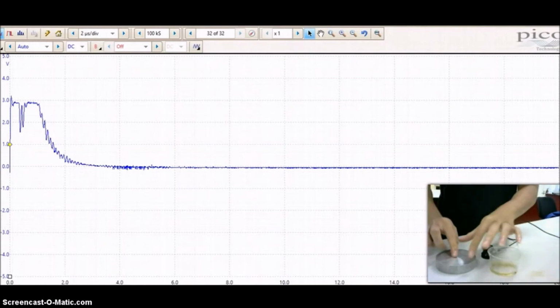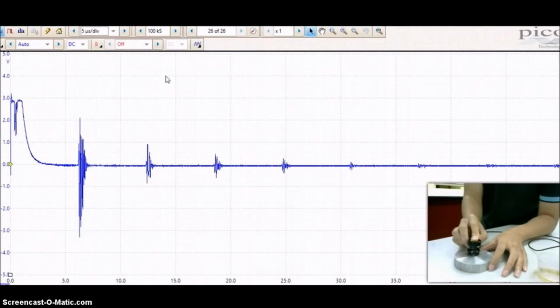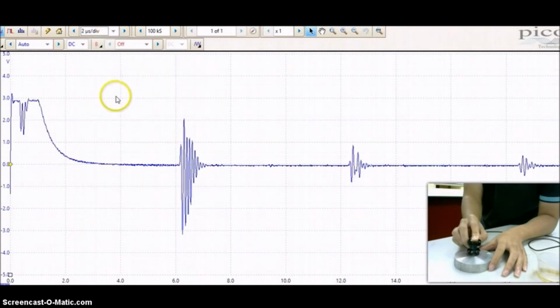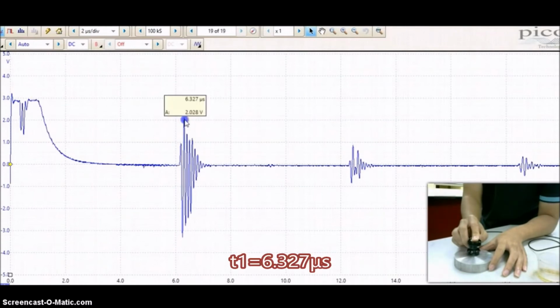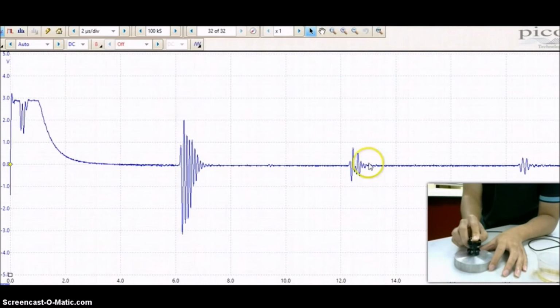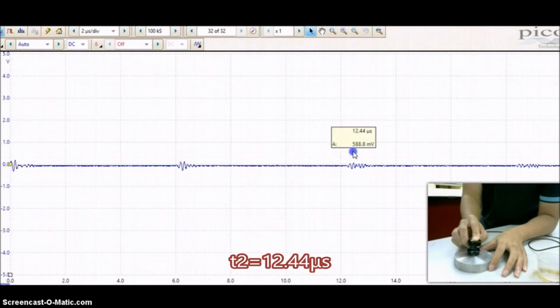First of all, we must apply oil on the specimen. Then we put the transducer on the specimen to find the time. We use 2 microseconds per division to find the time. The first backwall echo is 6.327 microseconds. And for the second backwall echo, the time is 12.44 microseconds.